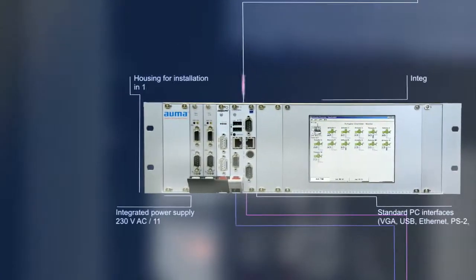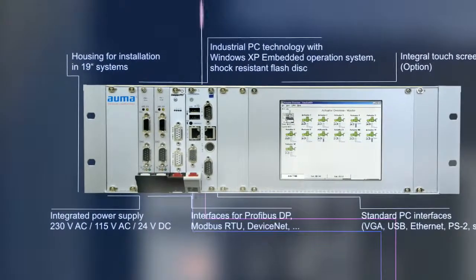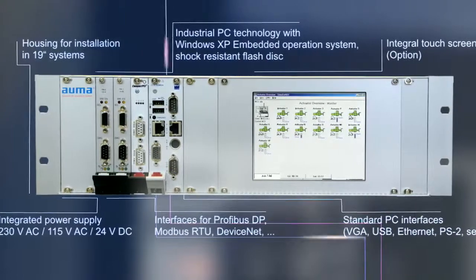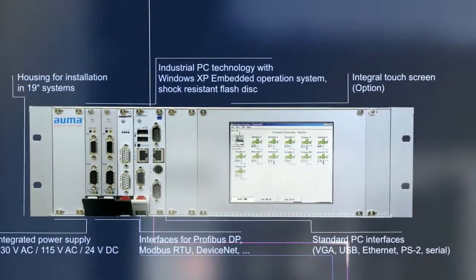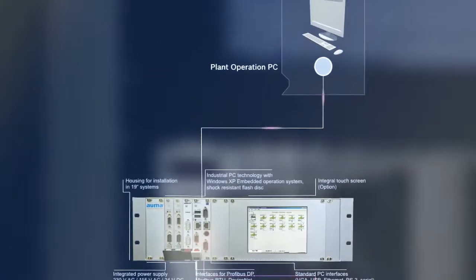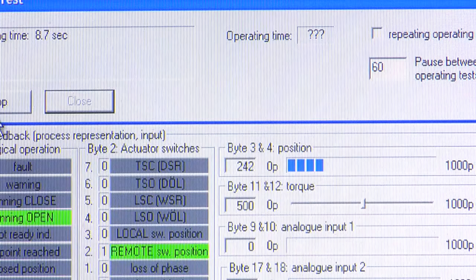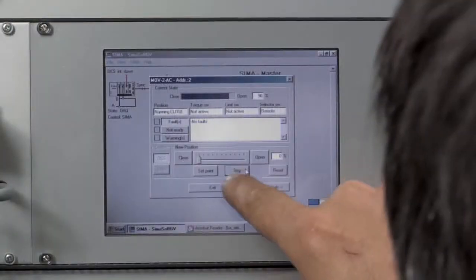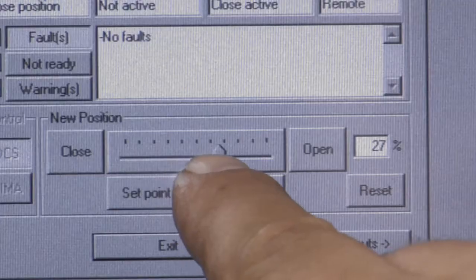They optimize the data transmission and work as protocol converters. In this application, the SIMA also acts as data concentrator. Only respectively required data is transmitted to the superordinate DCS. This way the DCS can focus on other tasks. Thanks to this AUMA technology, parts of the plant can be retrofitted, put into service and tested without requiring the connection to the superordinate DCS.